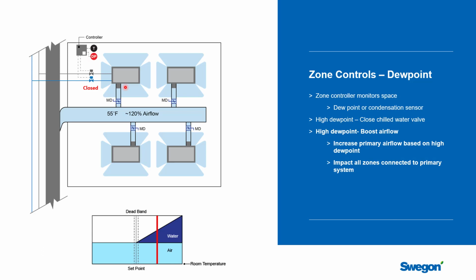And so what would happen here is, in the same situation where we have an increase in the dew point and it's starting to get us in trouble, and the dew point sensor is showing that the dew point is being closely approached in the space, then what you do is use that signal to go back to the air handling unit and say, don't operate at design airflow rate, step up to 120% of design airflow, and that will drive air not just into this zone, but every zone that that air handling unit serves. And what that'll do for you is help dry the building out.